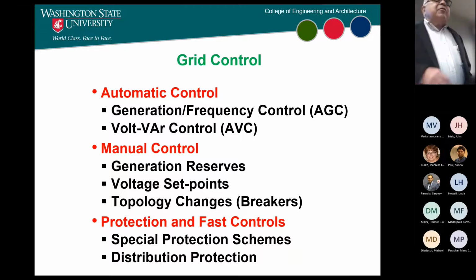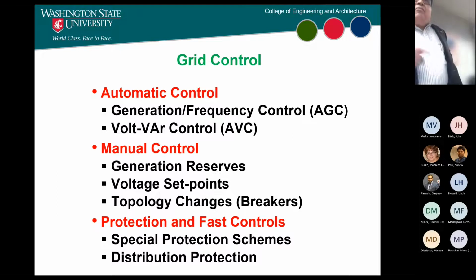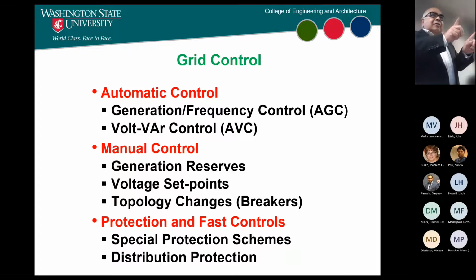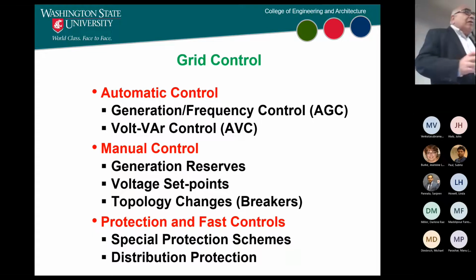Now they have special protection schemes, because you can bring a lot of data into a protective system, a protective relay, from far away, which didn't used to be the case. It used to be mostly local, but now you can even get PMU data feeding into the relays. So if you start seeing angles moving too fast away from each other, you open up the breakers or open up the line where it's going unstable, and those are called special protection schemes.